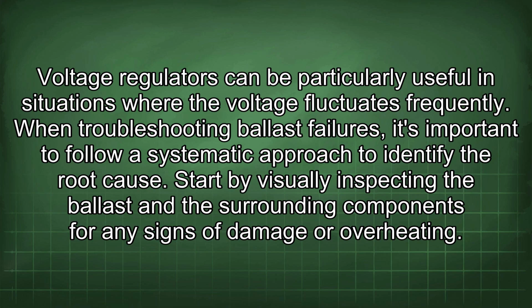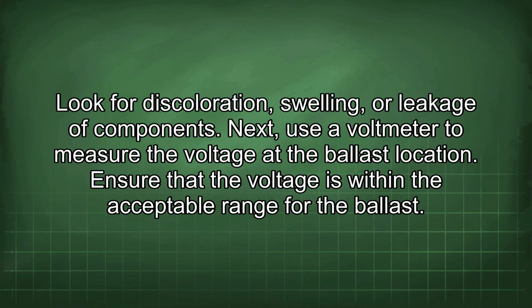Start by visually inspecting the ballast and the surrounding components for any signs of damage or overheating. Look for discoloration, swelling, or leakage of components. Next, use a voltmeter to measure the voltage at the ballast location. Ensure that the voltage is within the acceptable range for the ballast.